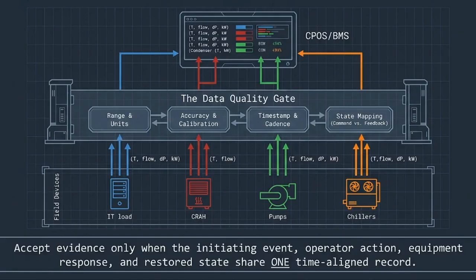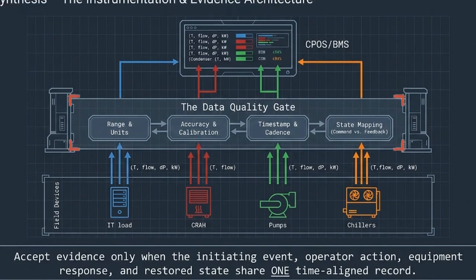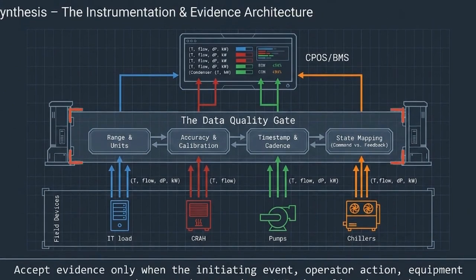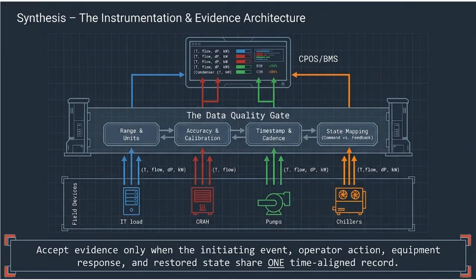Physical reassembly is only half the job. Before a system can return to automatic control, its signals must pass through the data quality gate to verify range, accuracy, and calibration. The strict rule for acceptance is that the initiating event, the operator's action, the equipment's physical response, and the restored state must all share one time-aligned digital record. Without synchronized, calibrated telemetry proving that the restoration holds under a representative IT load, the maintenance intervention is operationally incomplete.